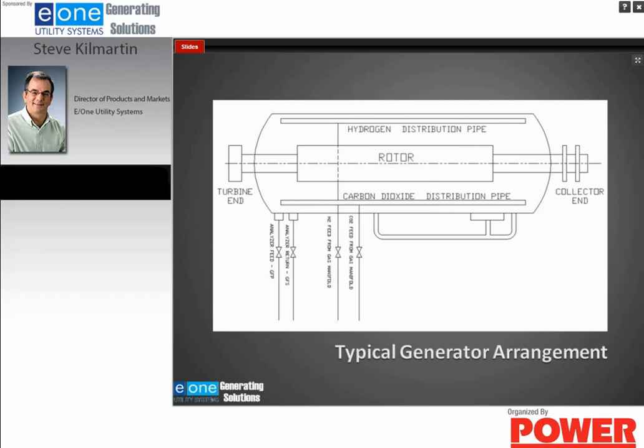After I have this generator filled with carbon dioxide, now I want to get rid of the carbon dioxide and put hydrogen in there. So what I'm going to do is connect my hydrogen feed to my hydrogen supply. I'm going to move my analyzer now to the CO2 feed line that's going to vent, and I'm going to start to put hydrogen in through the hydrogen distribution pipe. Because hydrogen is a lighter gas, it's going to force the CO2, which is the heavier gas, out the bottom distribution pipe. And again, my analyzer that I'm using to read the gas in the generator will not see hydrogen until hydrogen has completely forced the carbon dioxide out of the distribution pipe in the bottom of the generator.